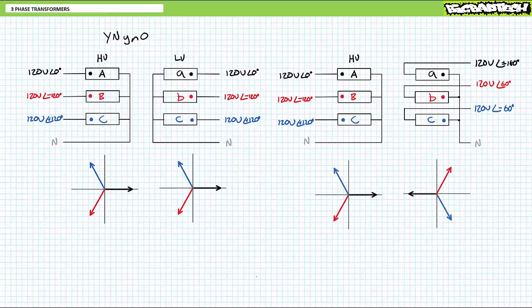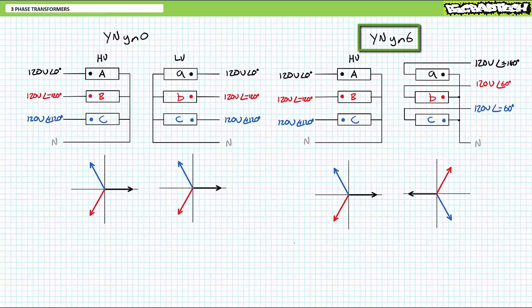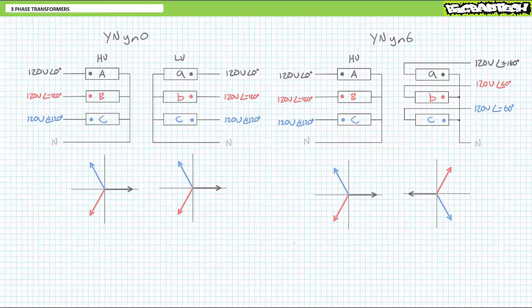If we were to draw the phasor diagram for the high-voltage input and low-voltage output, each phasor would be the polar opposite of one another — pointing left when they were pointing right, pointing up when they were pointing down. Given the low-voltage outputs exhibit a 180-degree shift with respect to the high-voltage inputs, you'd think they'd call this a YN,YN180, but they don't. They call it a YN,YN6, where 6 means 180 degrees using what is known as clock notation. This can get confusing quickly, so it's a good time to introduce clock notation and explain standard three-phase transformer naming conventions.